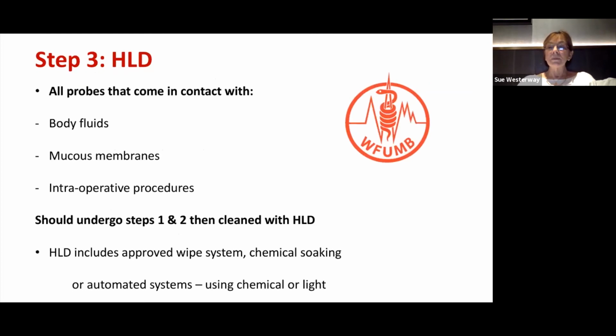Step 3, where required, is high-level disinfection, and that's for all probes that have come in contact with body fluid, mucous membranes, or intraoperative procedures. They should undergo steps 1 and 2 and then be cleaned with high-level disinfection. High-level disinfection includes approved wipe systems, chemical soaking, or automated systems using chemical or light.